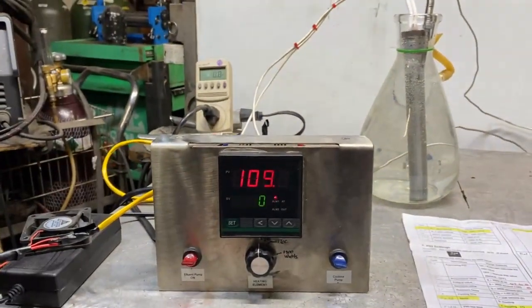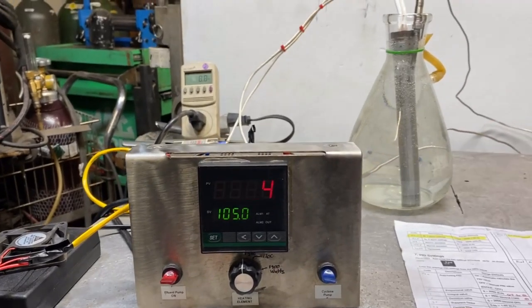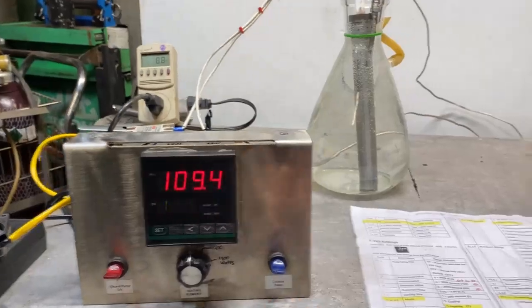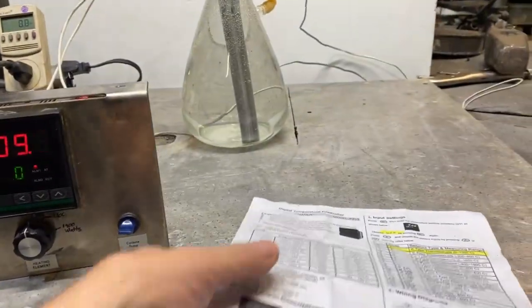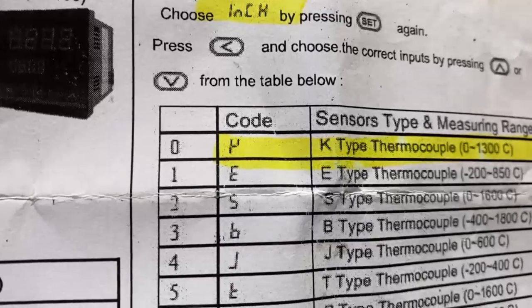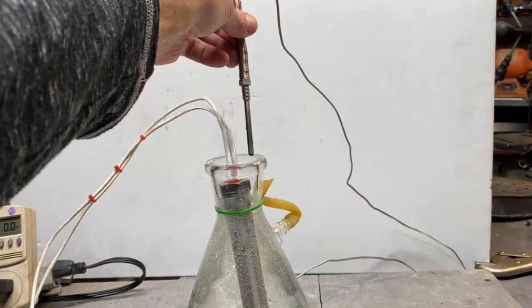So Ken, to get right to the point, the first thing we need to do for you is to get the thermocouple set up. The way you get the thermocouple set for the proper thermocouple - in this case, you have a K-type thermocouple. So we're going to want to see this backwards Y symbol. This is a K-type thermocouple.